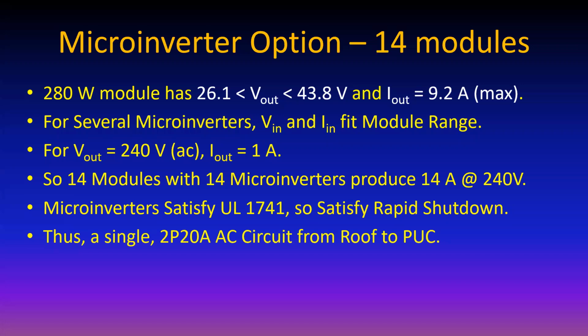So 2-pole 20 amp, and you're in, as long as there's room for an extra 2-pole breaker in the main distribution panel. If not, you do a tap with a 2-pole 20 amp circuit breaker, or a couple of fuses if you want to use a fuse disconnect, in order to get into the tap connection.